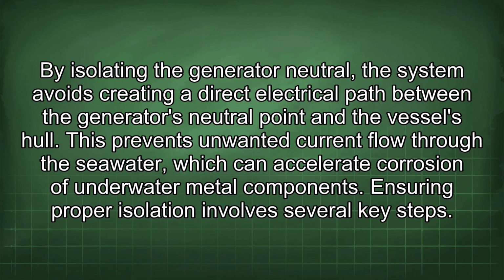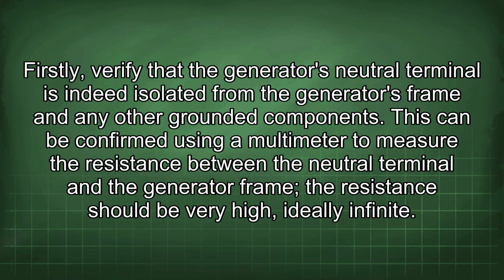Ensuring proper isolation involves several key steps. Firstly, verify that the generator's neutral terminal is indeed isolated from the generator's frame and any other grounded component. This can be confirmed using a multimeter to measure the resistance between the neutral terminal and the generator frame. The resistance should be very high, ideally infinite.